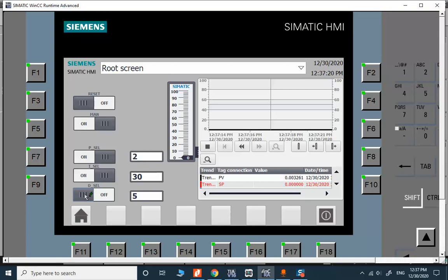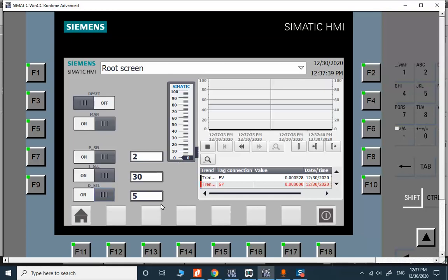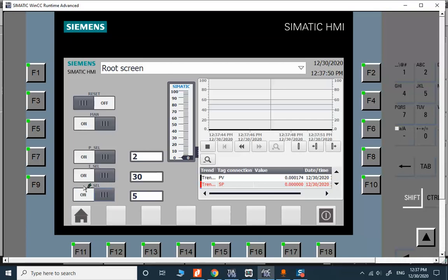The D selection is off in most of the industrial applications, but if your process is sluggish, it's slow, the time constant is higher than normal, you need to disable that and change the parameters.